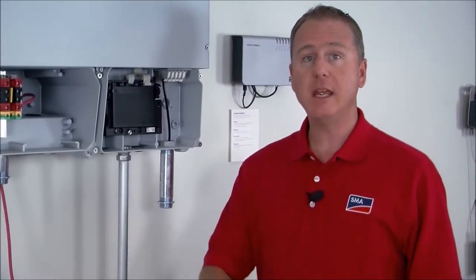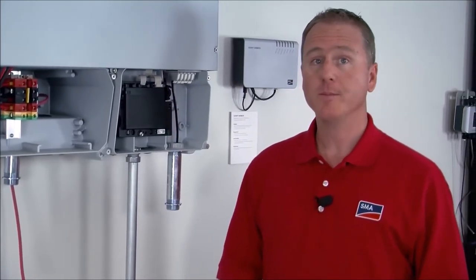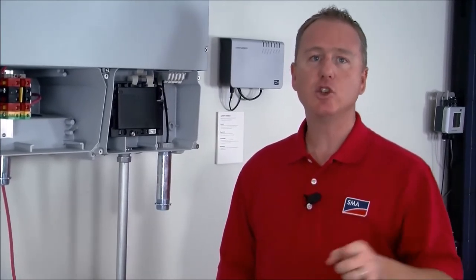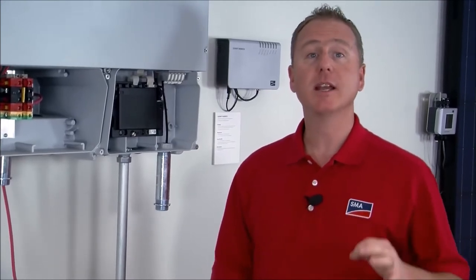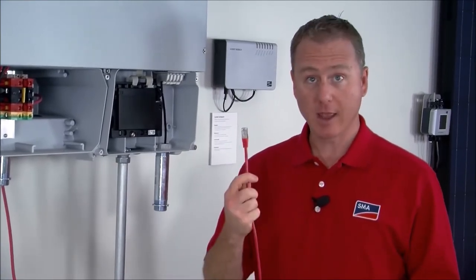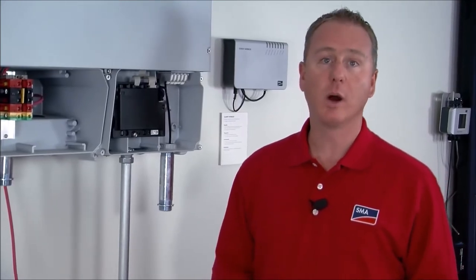So the last thing to do inside the tri-power is to install your communication wire. Now the speedwire module behind the LCD display is factory installed in Denver, Colorado so all you have to do is run the ethernet from the customer's router or the cluster controller and run it into the speedwire module. Now if you have multiple tri-powers then you're just going to daisy chain the tri-powers together. We cover this in another tech tip video but for now let me run my ethernet cable up through the conduit and connect it into one of the two ports on the speedwire module.